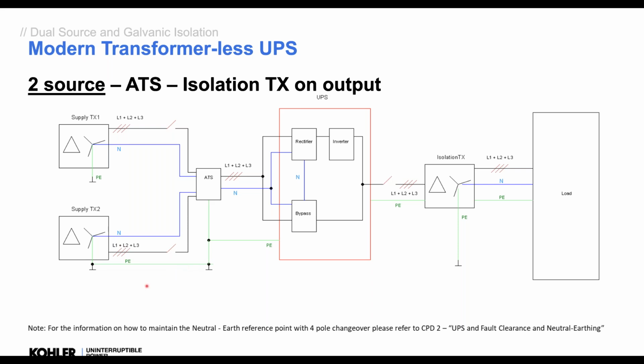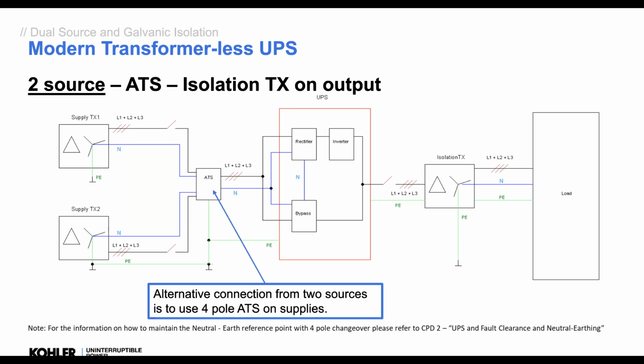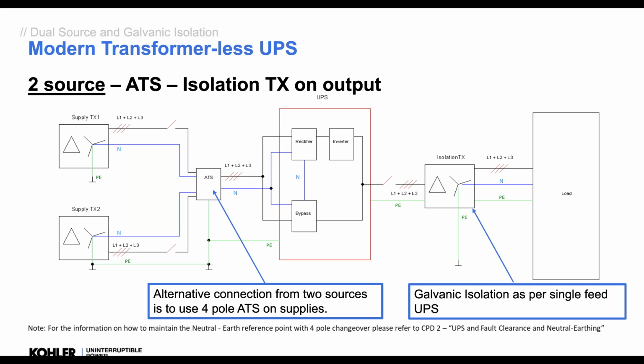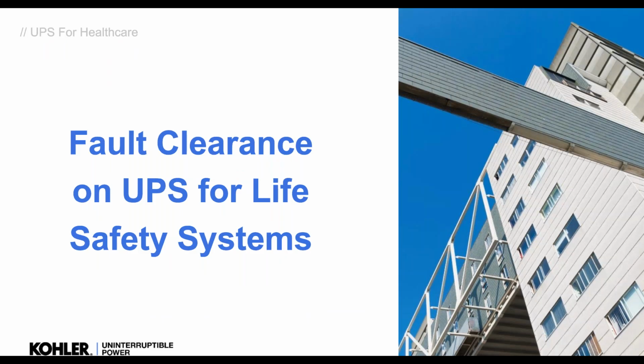But it depends where you want the dual supply. Do you want it at final circuit, or do you want it at central UPSs? Okay. So the UPS will have the ATS for the changeover for the dual supplies, and the galvanic isolation transformer to recreate the neutral earth, as you would on any type of UPS from any supplier. All right. Okay.